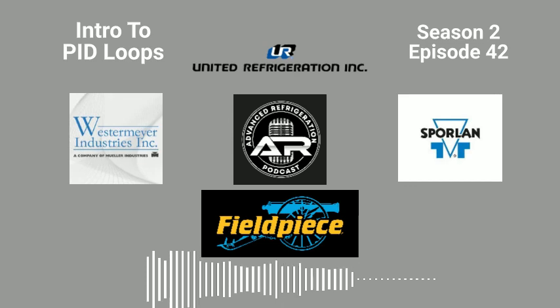You have a summer set point, you have a winter set point, because in the summertime, you're going to have a way bigger load in your flash tank than the winter. So you're going to have way more hunting in the winter. When you get to CO2 stuff, when you guys start to see more CO2 stuff, it is nothing but PI loops and PID tuning. And you've got to remember, every single valve in a store is electronic, unless they're pulse valves.